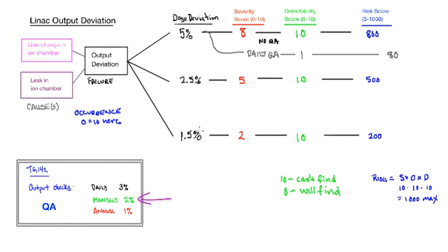Let's move on to monthly then. So that's 2% sensitivity. Again, you won't get this one, but you will get that one. Okay, so let's add it in, and we'll see how it affects this 2.5% deviation. We add in monthly QA as done according to this report, and the detectability of this becomes really good too. So it goes down to 1, let's say, and now we got 5 times 10 times 1, so 50. So it went down a lot by putting this QA in place, just as this one also went down a lot. The overall risk is much lower for these types of deviations.